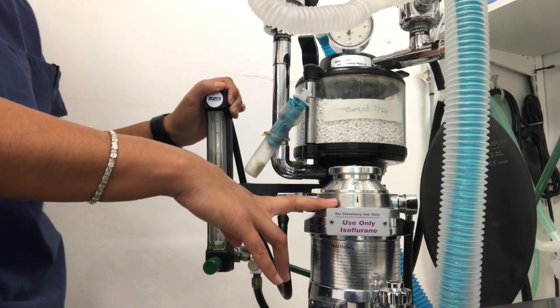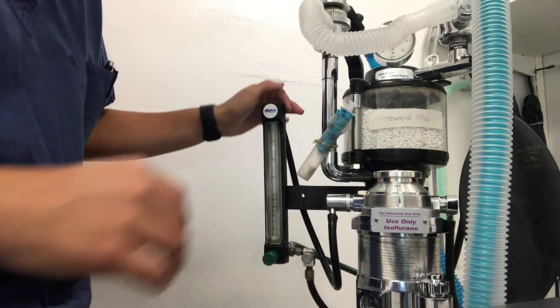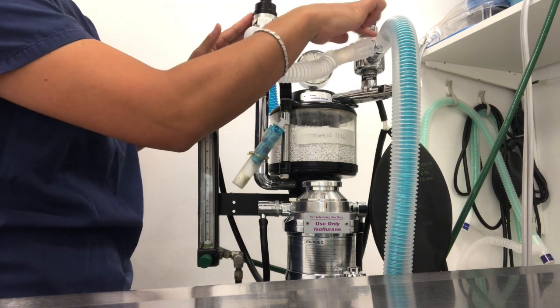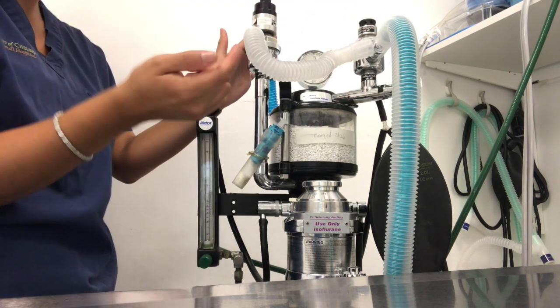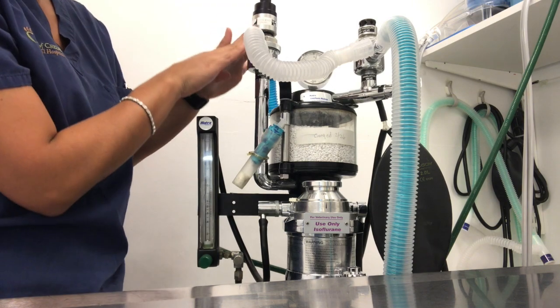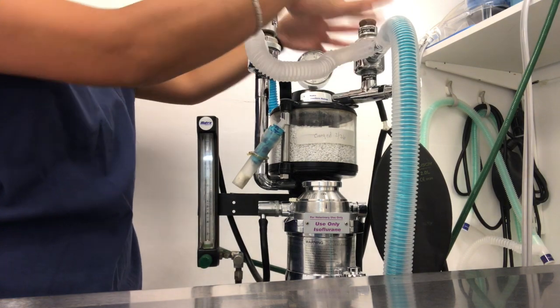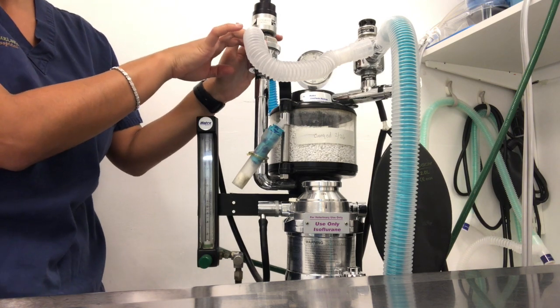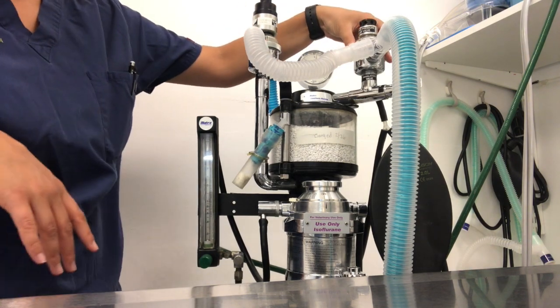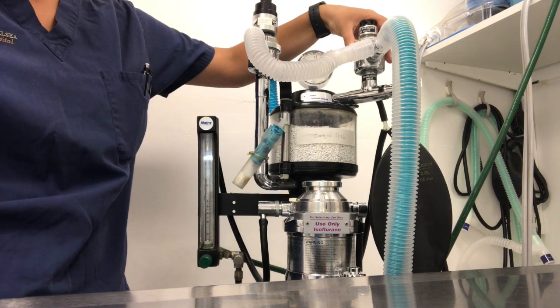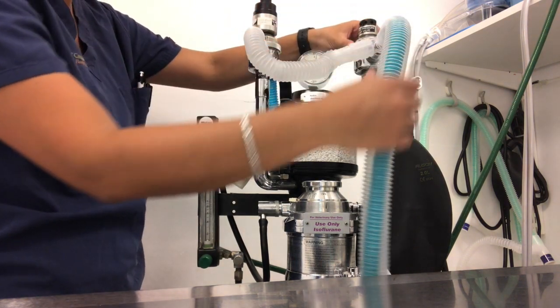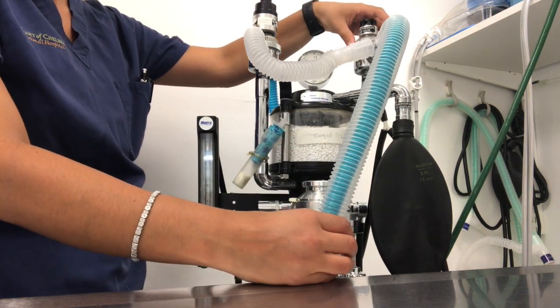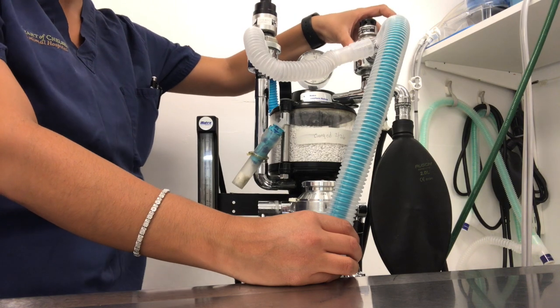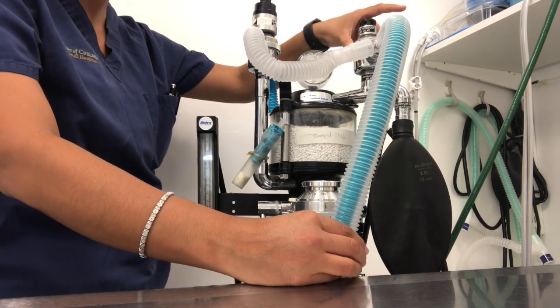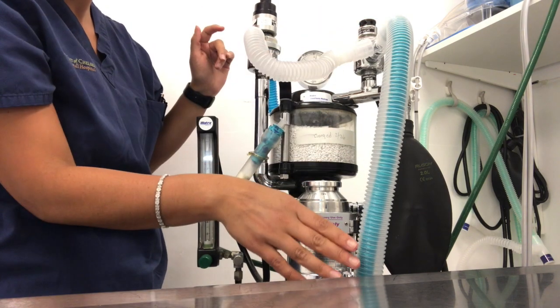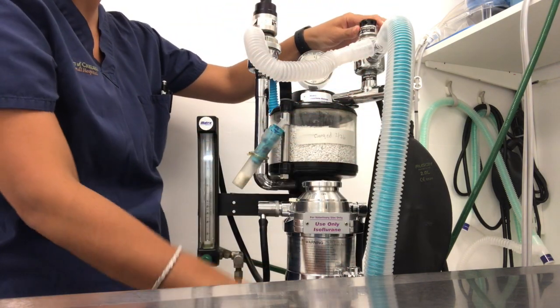The next is our inlet and our outlet ports, which we have right here. Both of these are unidirectional valves, so gases will only flow one way through them. This one is our exhalation valve, and this is our inhalation valve. I would probably start with our inhalation valve, which is on the right here. The inhalation valve is attached to our inhalation tube, as you can see right here. It opens when the patient breathes in and allows the anesthetic and the carrier gas to flow through the tube into the patient, in that direction.